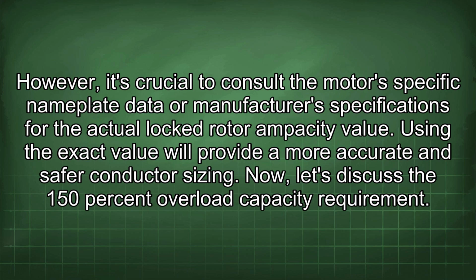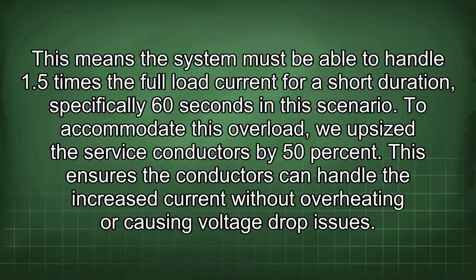Now let's discuss the 150% overload capacity requirement. This means the system must be able to handle 1.5 times the full load current for a short duration, specifically 60 seconds in this scenario. To accommodate this overload, we upsize the service conductors by 50%. This ensures the conductors can handle the increased current without overheating or causing voltage drop issues.